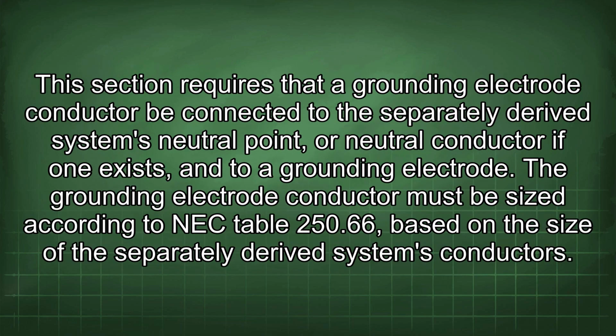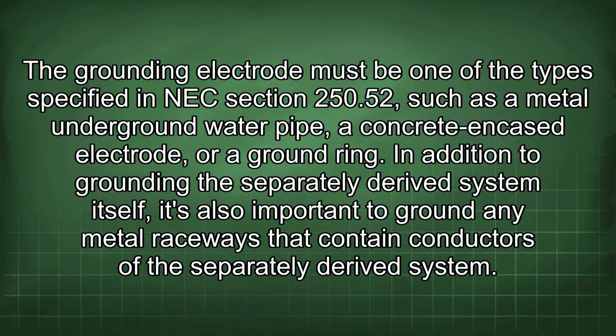This section requires that a grounding electrode conductor be connected to the separately derived system's neutral point, or neutral conductor if one exists, and to a grounding electrode. The grounding electrode conductor must be sized according to NEC table 250.66, based on the size of the separately derived system's conductors. The grounding electrode must be one of the types specified in NEC section 250.52, such as a metal underground water pipe, a concrete encased electrode, or a ground ring.